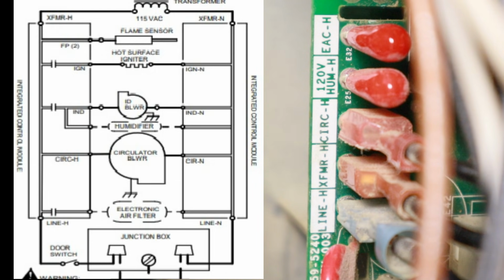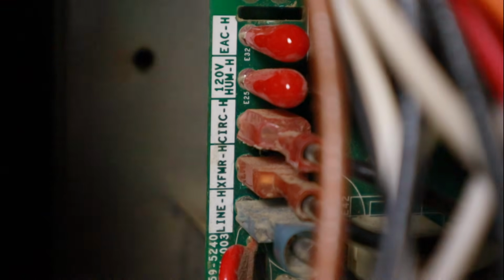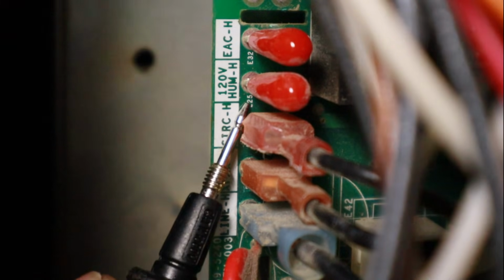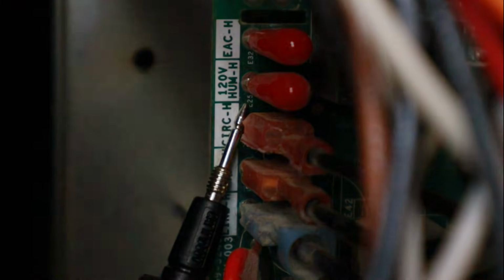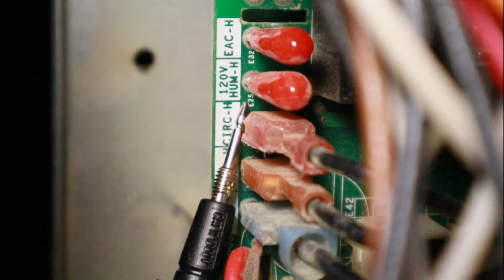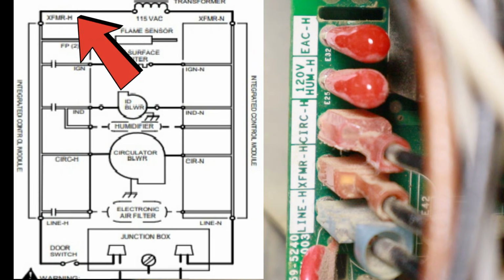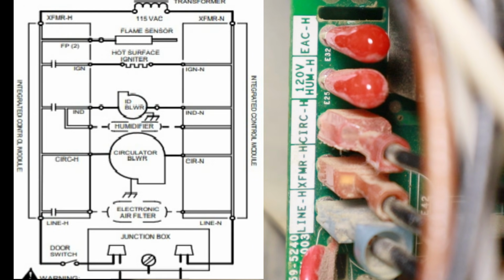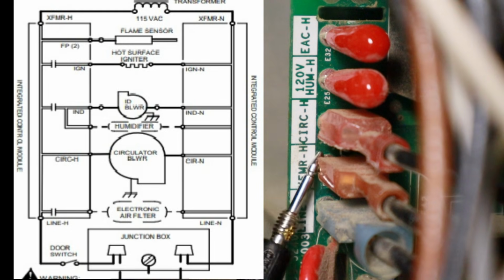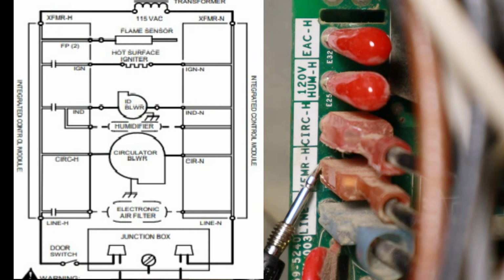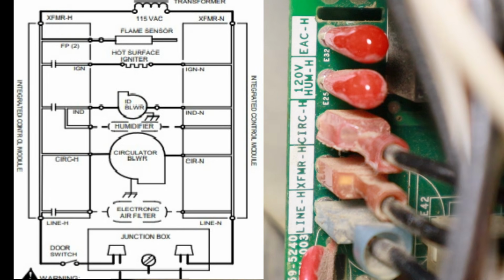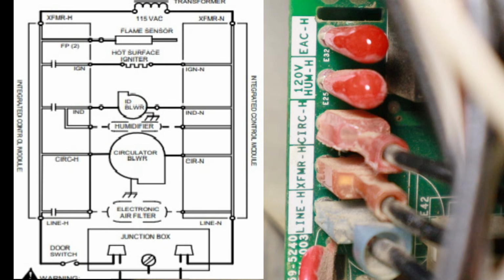So for example, circ H on this ladder diagram has no switch in it. So what that basically means, if I were to take my probes and test for power right now on the circ H terminal, I should read about 124 volts there. So I'll take my probe, I will put it on circ H, I will go to a ground, and you can hear my multimeter going off, and I have 125 volts there. Now the same thing is true for the transformer. You see there is no switch on this diagram, so it is wired directly off a line to the transformer. So if I were to take my meter, put it on that transformer terminal, go to ground, once again I'm reading 125.